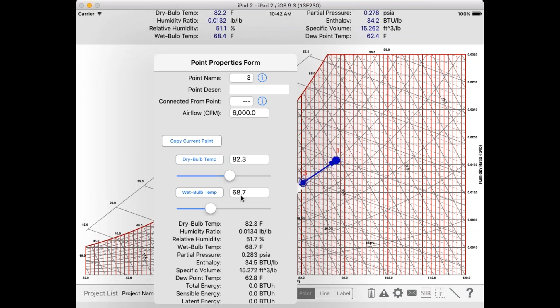Now some of you may be asking, when we do mixed air, do we take the airflows or do we take the masses? We indeed take the mass, because if you think about it, the density of air at this state point versus this state point varies. It doesn't vary by much, but it does vary. So if we just did the ratio of the airflows, it would be a little inaccurate. Instead, we take into account the density of air at each point, calculate the mass of air, and then do the ratios to calculate our mixed air. That is the more accurate way to do it, and indeed we do it that way.